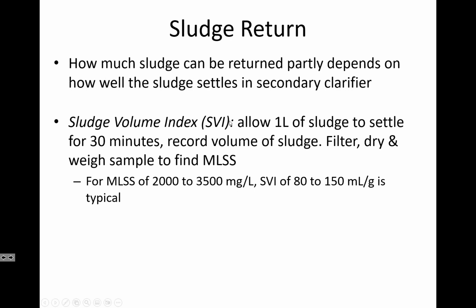So what you're doing in calculating the sludge volume index is you're just seeing how quickly that sludge blanket can allow water to pass through it and how quickly the sludge blanket can compress. So it's very different from particulate settling. And I think in that earlier portion we talked about how an SVI, sludge volume index, of between 80 to 150 is kind of in the sweet spot of, in a 30-minute period, the volume that's occupied per gram of sludge.